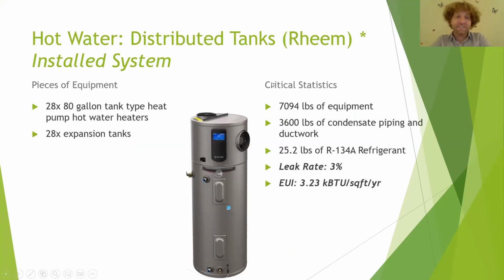So the first system we analyzed was distributed tanks, and these have been around for the longest time. Well, out of all the heat pumps, these have been around the longest. So this was actually the only system we had at the time to do heat pump hot water heating for this building. But it's relatively simple because you don't have a circulation loop or anything like that. It's just a heat pump per 1 or 2 apartments, and it's a package unit. Doesn't use a ton of refrigerant, and doesn't leak a whole lot.